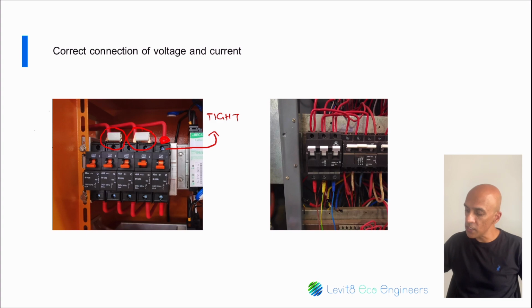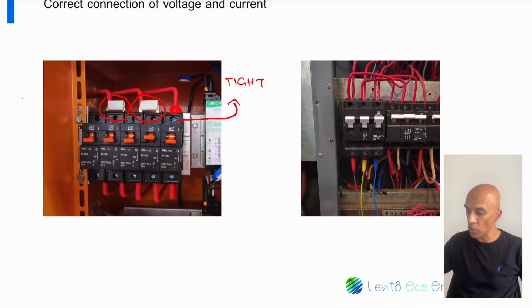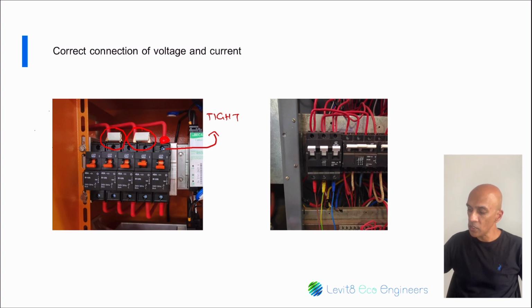Now, if you have a look at this photo alongside here, this is one of the examples I've found several times in my measurement experience. What happens here is there's a spare three-phase circuit breaker in the panel, and it's not being used for anything, but it does have supply coming in at the top of the breaker. So all I do is I take my banana plugs and I connect them into the bottom terminals, tighten the terminals and switch on, and there I've got three-phase voltages being measured. It's a good secure connection and very safe.